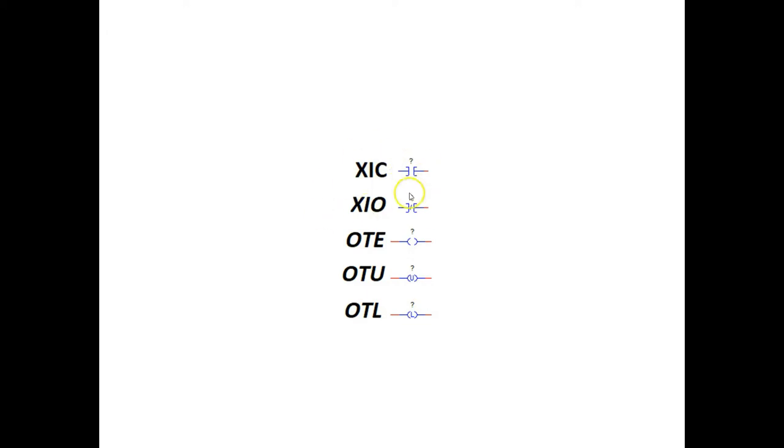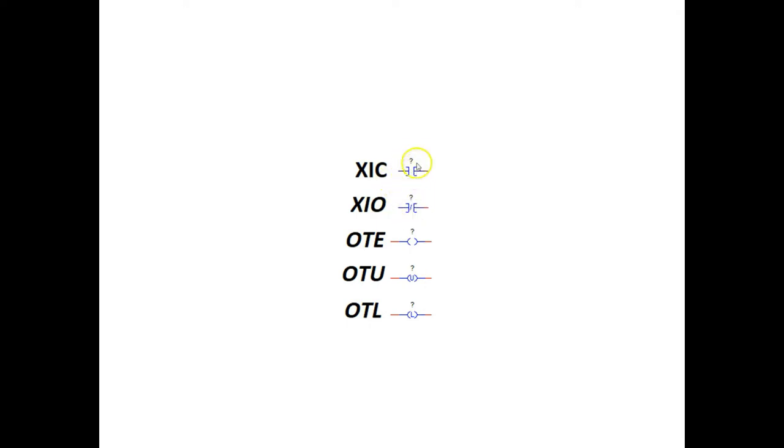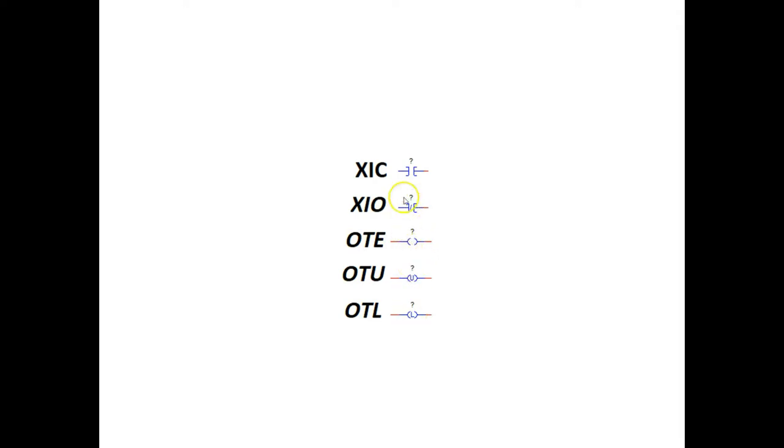But let's start by talking about XIC and XIO in particular because they're a little strange. Allen Bradley does things that are just a little different than what you would think. Looking at this you would think that would be a normally open contact and this would be a normally closed contact. But actually this is an XIC, examined if closed, and this is an XIO, examined if open. And this is our output energize or OTE bit. These are outputs. XIC and XIO are inputs. They're going to go on the left side of the rung. These are on the right side of the rung.